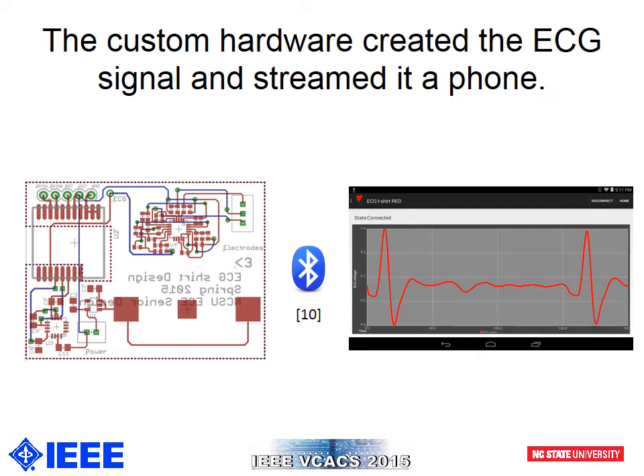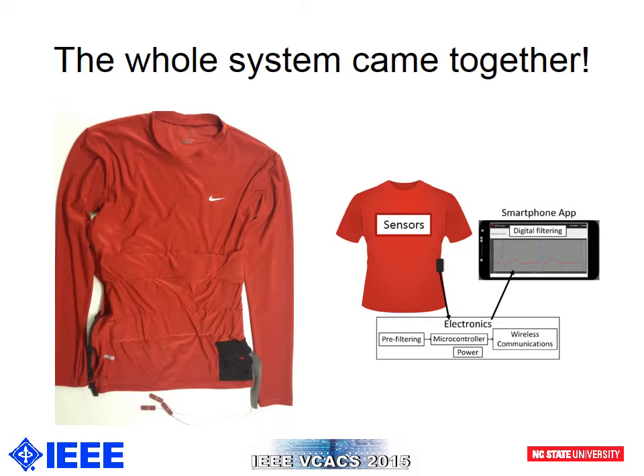Our custom hardware fit in a small enclosure on the shirt. We designed a small PCB that contained an RFduino module, which is a combined Bluetooth Low Energy microcontroller module, power supply, and Analog Devices AD8232 ECG front-end chip. The front-end chip sent the ECG signal to the microcontroller, where it was then sent via Bluetooth to a custom Android application. The final prototype consisted of a tight-fitted shirt with textile electrodes located on the inside. The electronics are placed in a compartment on the side of the shirt. Wires come out of the electronics, go through the shirt through fabric channels, and are attached to the dry electrodes through conductive epoxy.